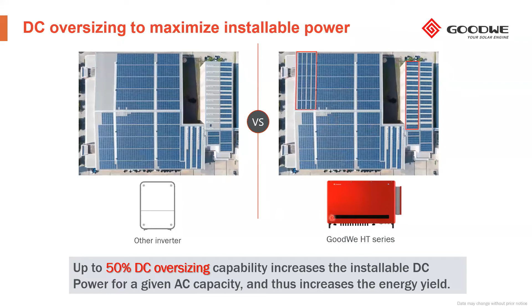For a given AC capacity, we can use more available surface by means of this feature, this capability of the inverter. The same concept, but in a different way, is that if we use the rooftop at maximum level, that means that we optimize the surface. That means that we compare a given DC power, right? We can reduce the number of inverters by means of this feature, the DC oversizing. And that is a positive impact in the CapEx.